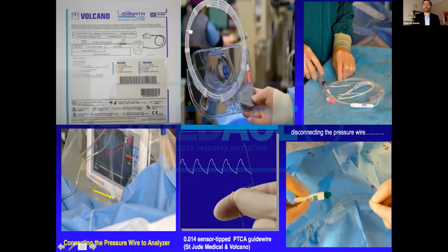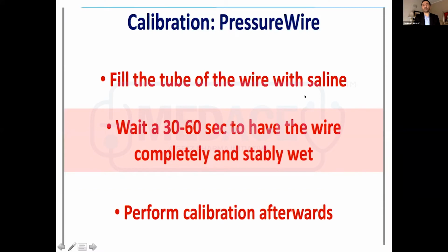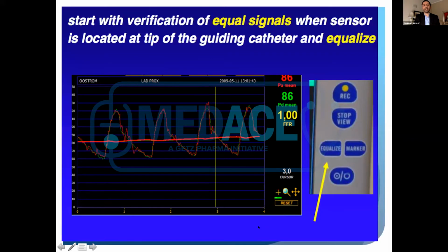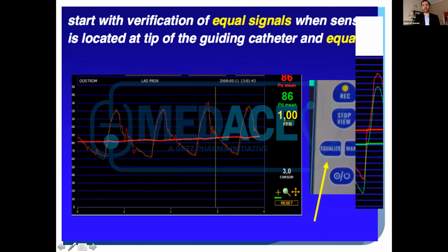And then after you've done the FFR measurements, you can actually disconnect it from the system and do a angioplasty over that wire. And this wire can be used multiple times for multi-vessel PCI, and post PCI also you can do measurements by reconnecting over here. So fill the tube of the wire with saline before zeroing. Wait for 30 to 60 seconds to have the wire completely and stably wet before performing calibration. That helps with proper zeroing. And when you are at the guide wire tip, make sure when you press the equalize button that these tracings are superimposed on each other, so you're equalized properly.